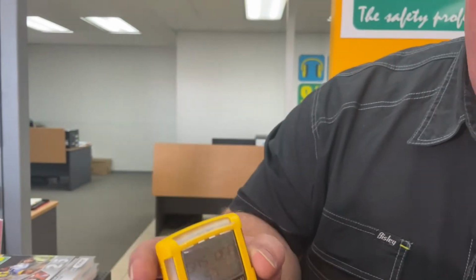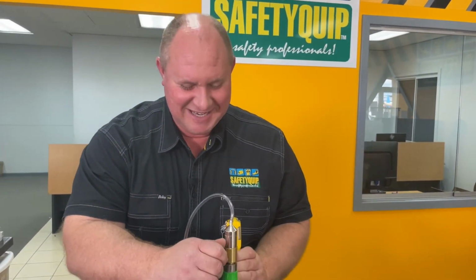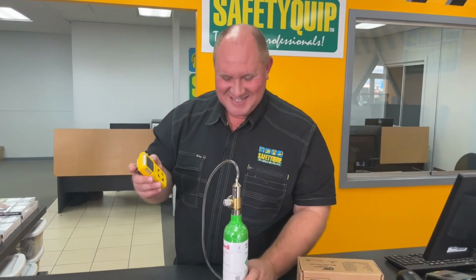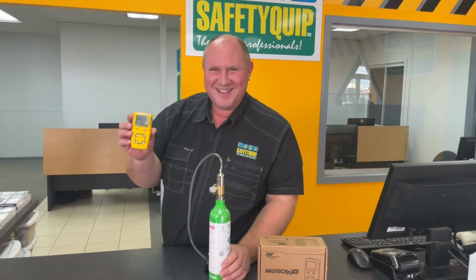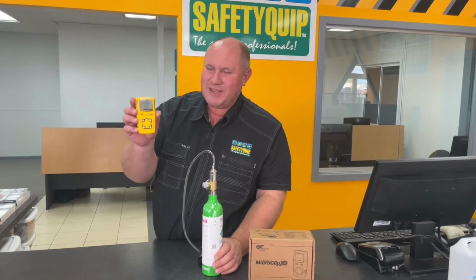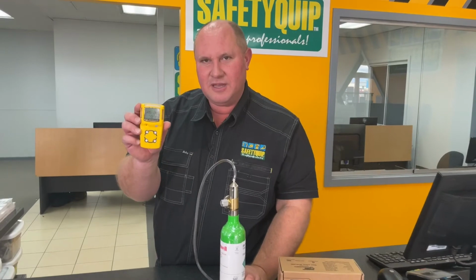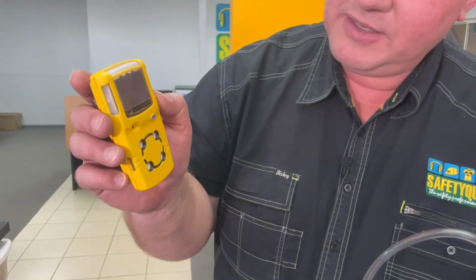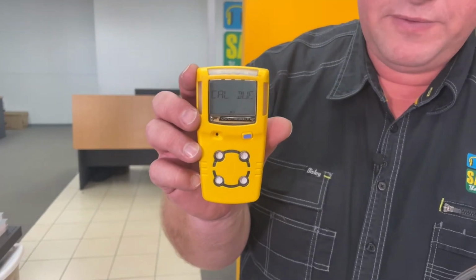Okay, I'll turn the gas off. It's important to turn that regulator off on your cylinder, or you'll be finding that there's no gas in there when you go to do it next time. So that'll count down, and what it's doing at the moment is purging out the gas. So it's just letting the gas dissipate so that the calibration process finishes.